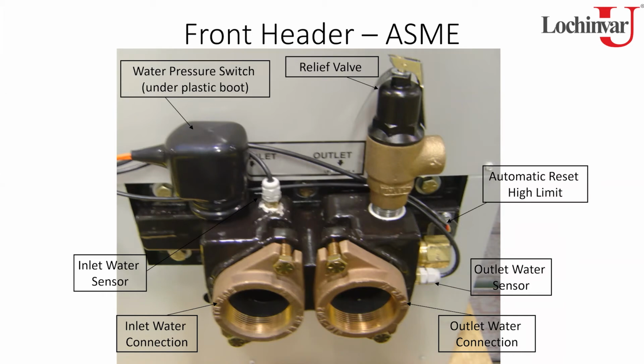So you can't see that on the non-ASME because everything is internal. On this one, you can see a part of it on the outside, but realistically, if you thought there were some issues, you're still probably going to have to take the header off and visually inspect and make sure everything's okay. Exactly. If you wanted to get to the actual plunger, yeah, you'd have to remove the head to get to it at that point. So, all right. So that's our heat exchanger.